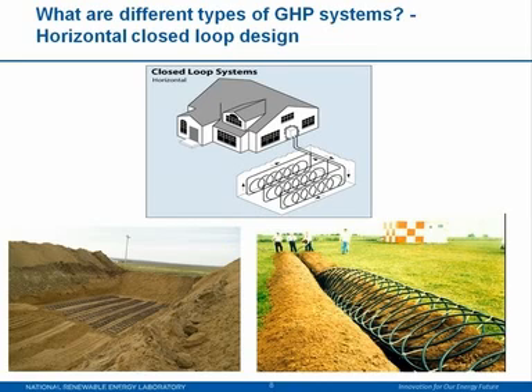The issue with the horizontal loop field design is that it requires more land than the next type I'll discuss, and it's more applicable to smaller buildings since you need more space. A huge structure would need a lot of land, and if you have the land available, you probably can do it, but then you're also talking about the cost of excavating a large amount of space. These systems are generally less expensive than the next type and require less specialized skill and equipment to install, so contractors are more widely available to do this type of orientation.